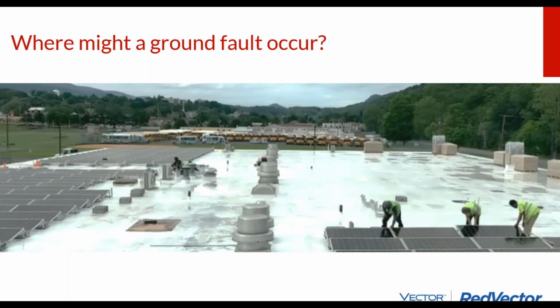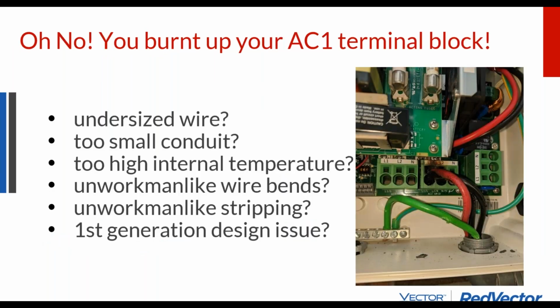For whatever reason, there's no code that I know of governing pools of water underneath 1,000-volt solar electrical systems, and maybe there should be, but that is to drive home the fact that when you have electricity faulting to ground, that is called a ground fault. That can be what burns the hole in the roof and causes the building to burn down. So, workmanship is important. And in fact, most solar fires in the industry that have occurred and burned buildings down because of it have been on commercial rooftops. So just pay particular attention to water issues on the roof is my recommendation.